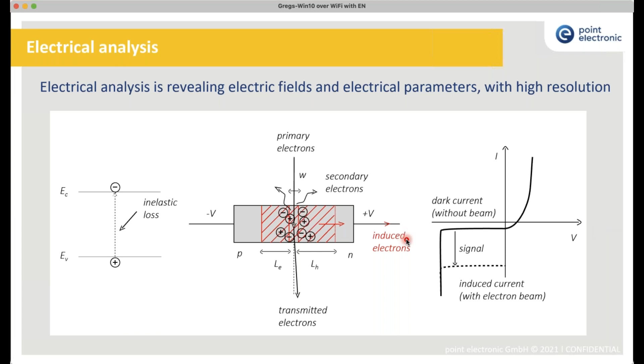What we can also do is apply a bias, and therefore we can make this depletion width wider or narrower, and we can see that in our imaging. So we can play with the device, we can interact with it, and see how the fields react to the operation. So you can look at fields in the same conditions as its normal operation.